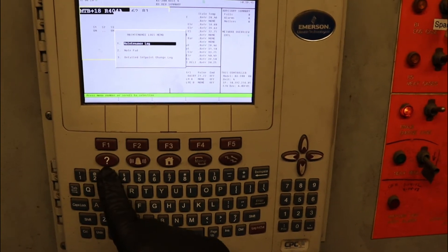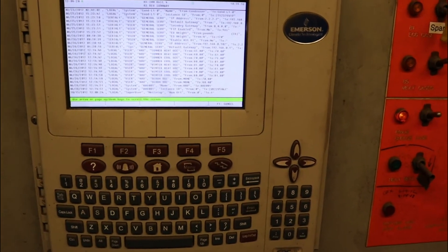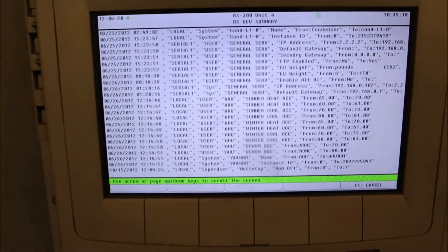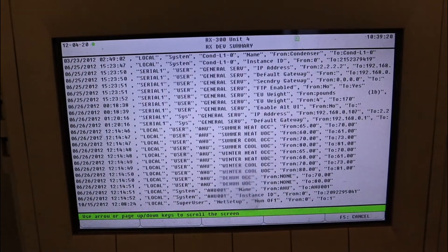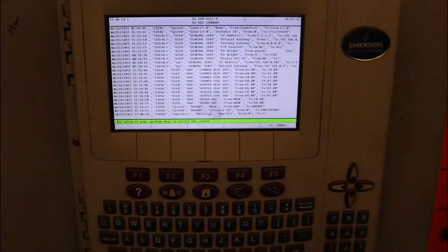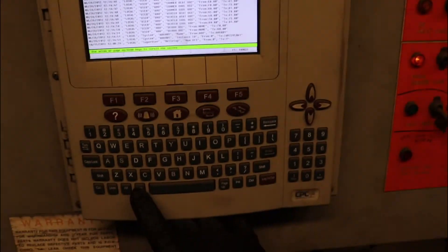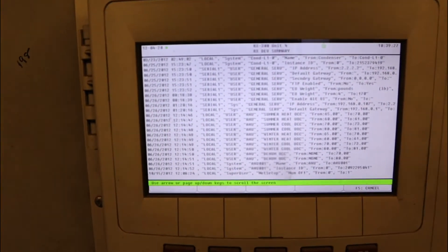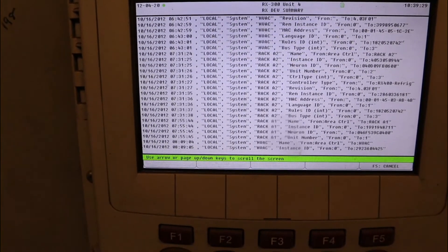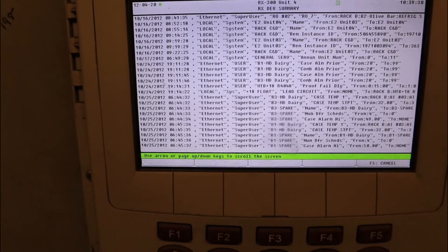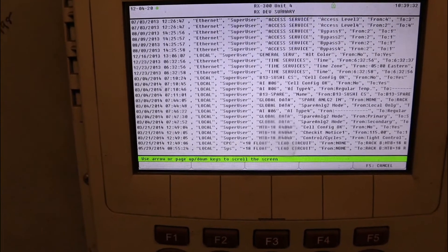Then you want to go to maintenance logs, number six. The very end, number three, detail setpoint change log. As you can see, this one goes all the way back to 2012 when the controller was installed. You want to hit page down to scroll through all the records, all the changes, all the offsets, all the way till today.